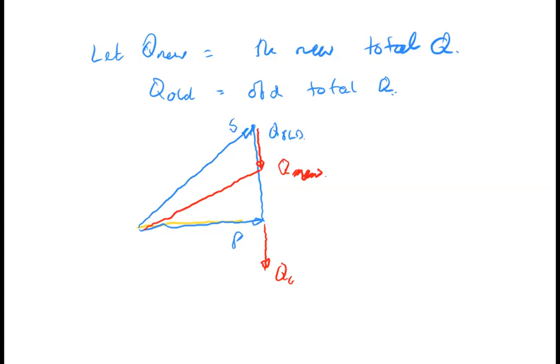The original cos theta power factor is 0.75, but for the new situation the power factor is 0.9. You can use that new power factor. The length of the P line doesn't change, so you can use that angle with the cosine of 0.9 to find Q, this distance here. If you take that away from the original Q old, you'll end up with the Q from the capacitor.